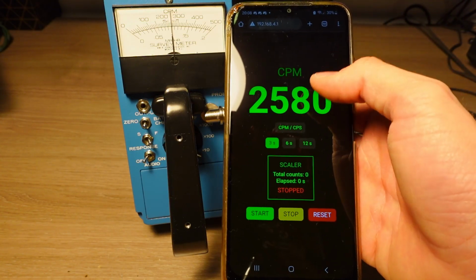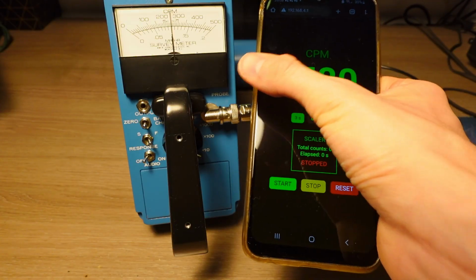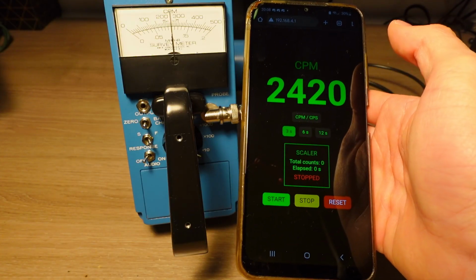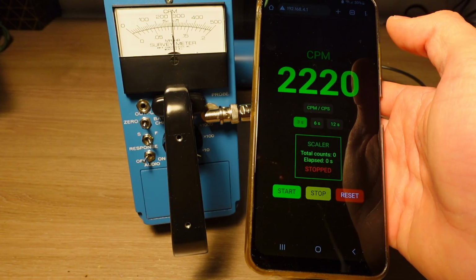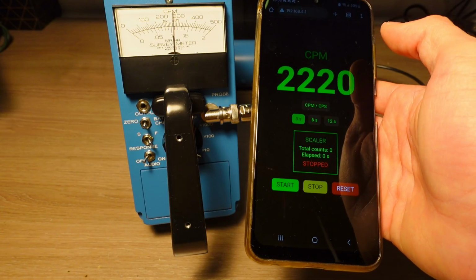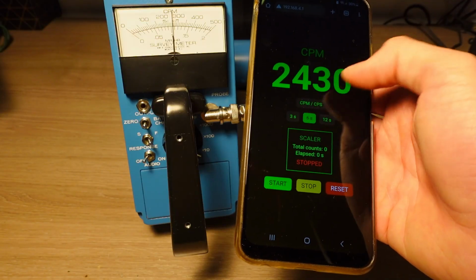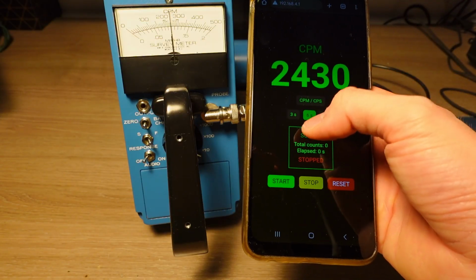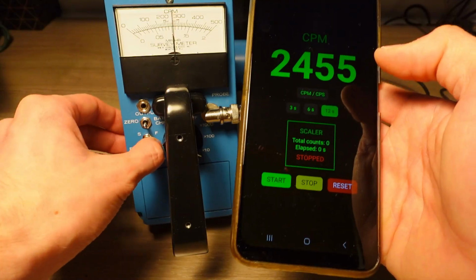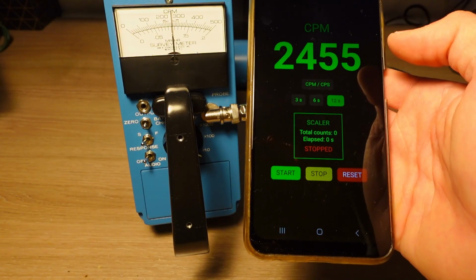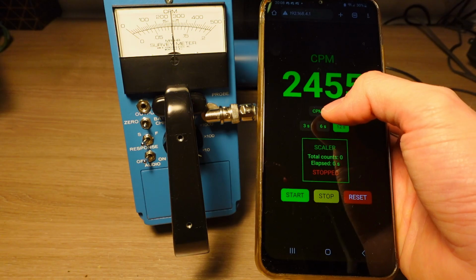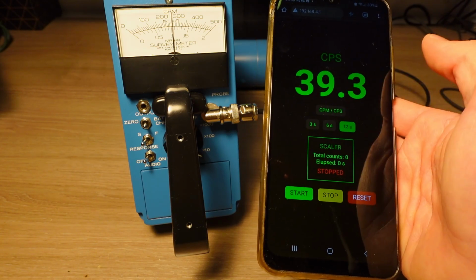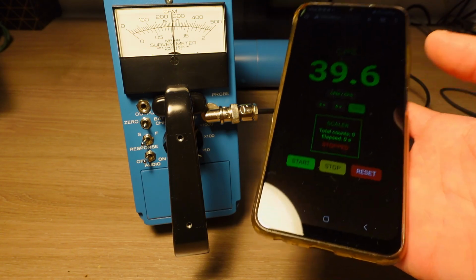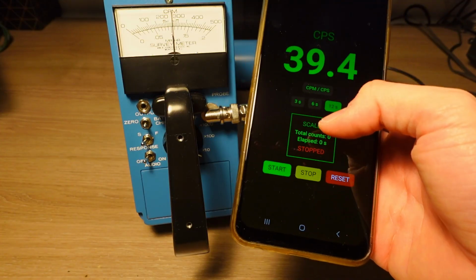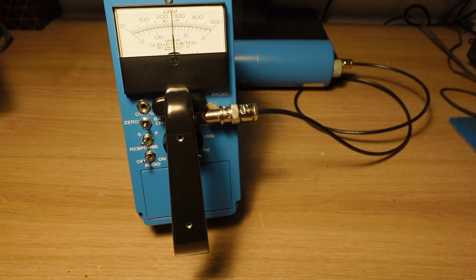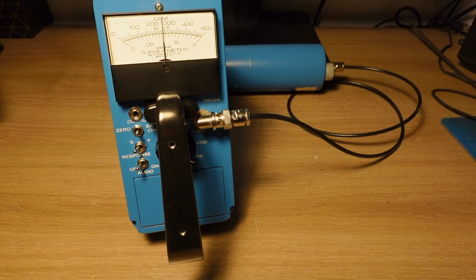So here we see the live count rate. You can see it matches the one shown on the meter, but it's more precise, of course, because this is all digitalized. We can change the integration time, for example, to have a slower or faster response, like we do on this analog part. And we can also change from CPM to CPS, so counts per second. But the most interesting part, in my opinion, and to show you this, I'll switch over to the computer as it's bigger.